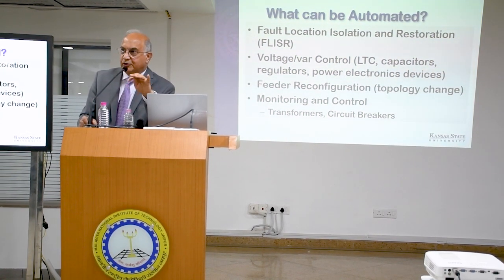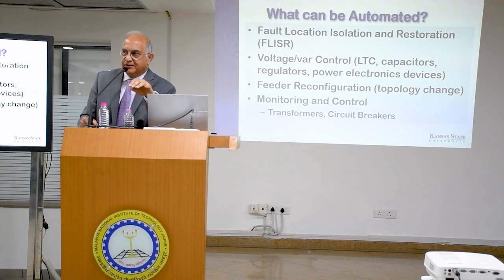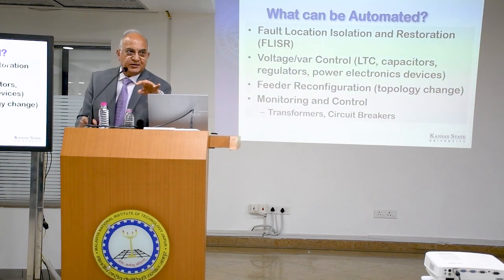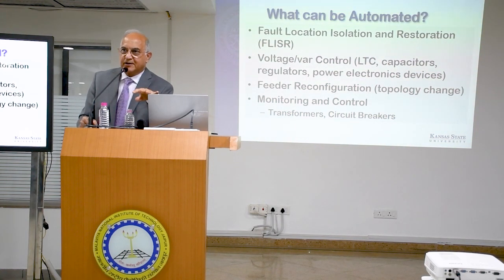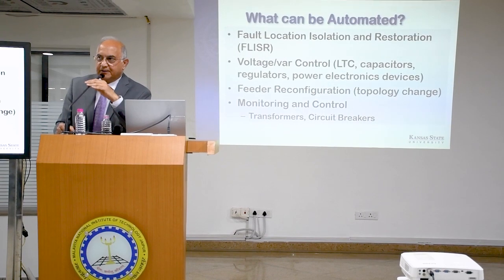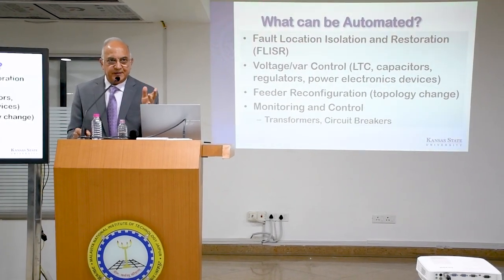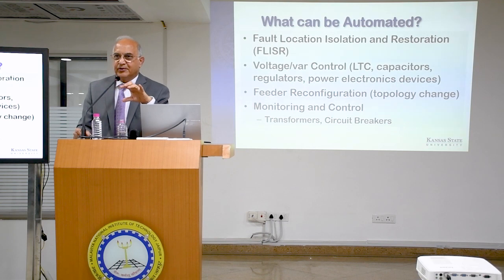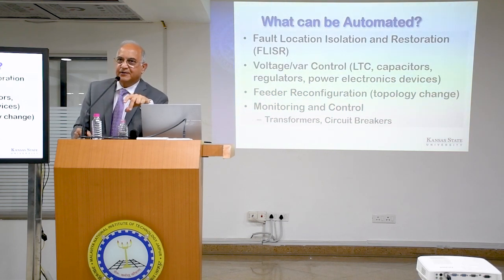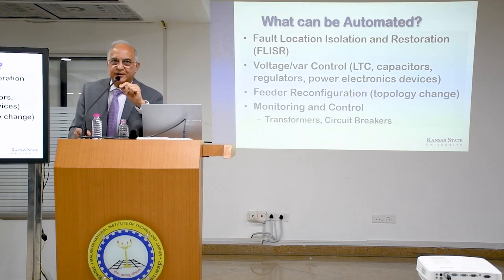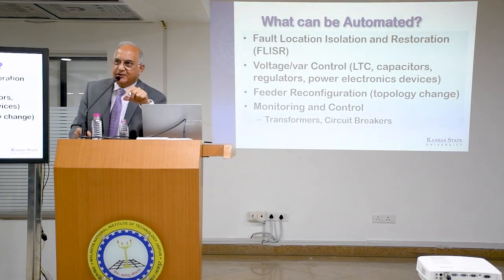The second thing is voltage VAR control. In the distribution system, they want to make sure customers get voltage at the right level. If the voltage is too low or too high, appliances can be damaged. So voltage VAR control is required to manage voltage within the proper range, which can be done by switching capacitors, controlling load tap changers on transformers, or switching electronic devices.